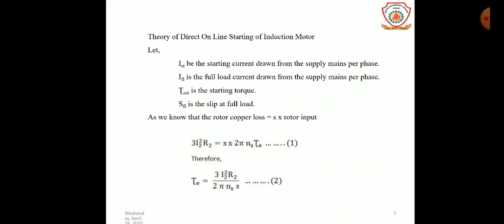The theory of direct online starting of an induction motor. Let us consider that I_ST is the starting current, I_FL is the full load current drawn from the supply mains per phase, T_ST is the starting torque, and S_full is the slip at full load. As we know, the copper loss equals slip times rotor input. Because this is a three-phase induction motor, we have 3 × I₂² × R₂.